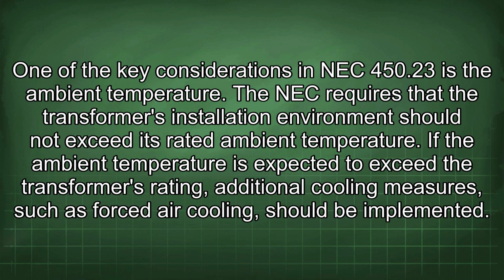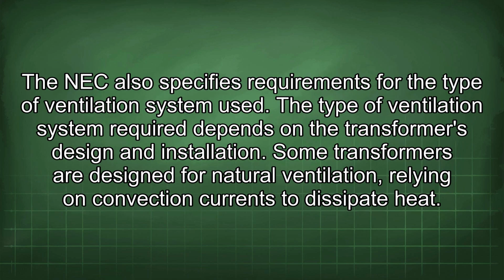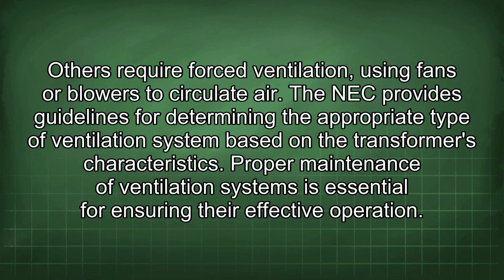be implemented. The NEC also specifies requirements for the type of ventilation system used. The type of ventilation system required depends on the transformer's design and installation. Some transformers are designed for natural ventilation, relying on convection currents to dissipate heat. Others require forced ventilation, using fans or blowers to circulate air. The NEC provides guidelines for determining the appropriate type of ventilation system based on the transformer's characteristics.